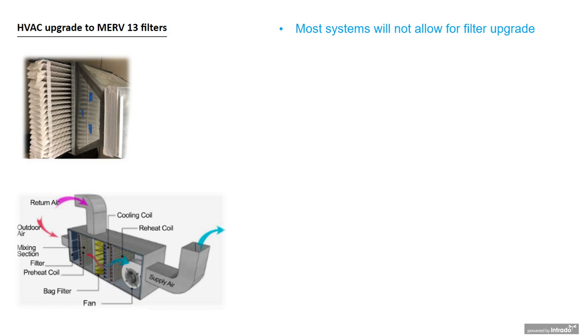Now, most systems will not allow for a filter upgrade. If you put a more robust filter in a system that was rated for, let's say, a MERV 7 filter, it's not going to be able to handle the pressure drop when adding a more heavily pleated filter such as a MERV 13 filter. So we have to factor that into our plans. And if upgraded, again, what is the impact to the heating and cooling loads?